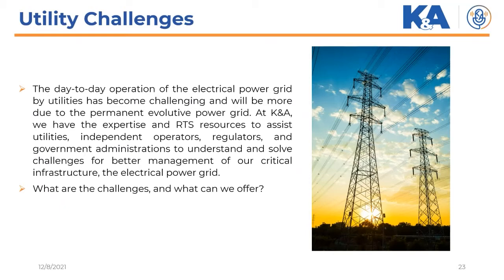From the traditional power grid where the flow of current was unidirectional, today the power grid has bi-directional power flow. The protection of the power grid has become so complex due to the bi-directional flow, complex due to the large change in short circuit level in different topologies of the power grid, complex due to the degradation of the power quality. The power grid has seen a large introduction of power electronic converters. Those power converters have inside them components switching at a very high frequency compared to the traditional 60 or 50 hertz. And those switchings have a negative effect on the quality of delivered electricity.